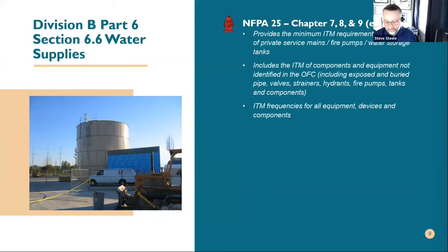They pulled out electric fire pumps, said, you know what, they're pretty reliable, comparable to a diesel. You don't have to get them up to operating temperature. They changed the duration of the run and even the frequency to monthly. And then now they step back, even in 25, you have to be very cautious. Is there enough water to run without fire department influence or addition to it, versus do you have to run it weekly versus monthly? So there are some things you do have to check to stay on top of with NFPA 25.